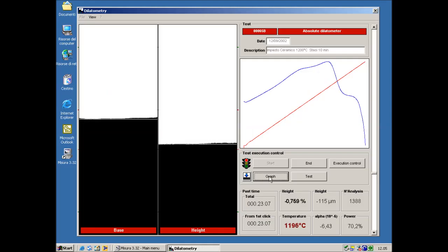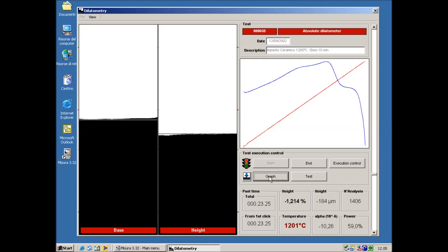This is the main window of the software during the measurement. Here we can follow a sintering test on a ceramic body. The 2 vertical windows on the left show the images of the top end of the sample and of the sample holding plate. On the right we have the expansion-contraction curve, colored in blue, measured on the sample as a function of time, and the temperature curve colored in red.